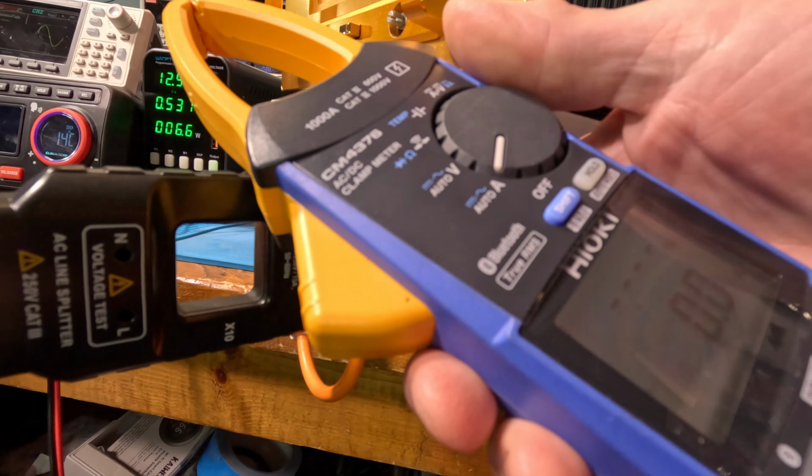Here, let's try the Hioki. Another meter meant for a lot of current, up to 600 amps. So let's see its accuracy down here at the lower currents. One thing, when I open up the jaws, it turns on a flashlight so I can see where to put it in. That's pretty cool. Automatically does that. So it's 1.21. The same as our IT Tech display. So these guys are pretty much rock on. So yeah, we like it.